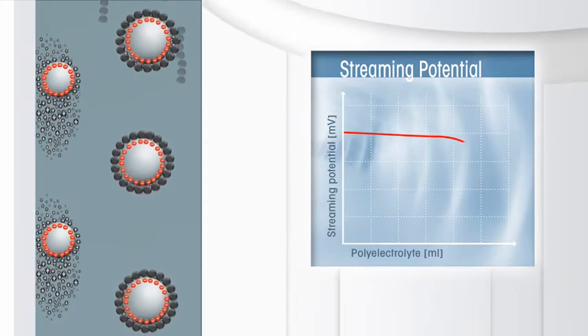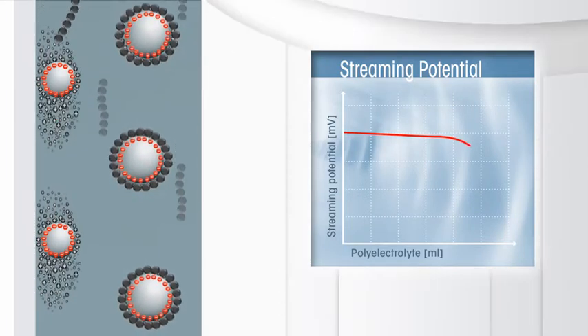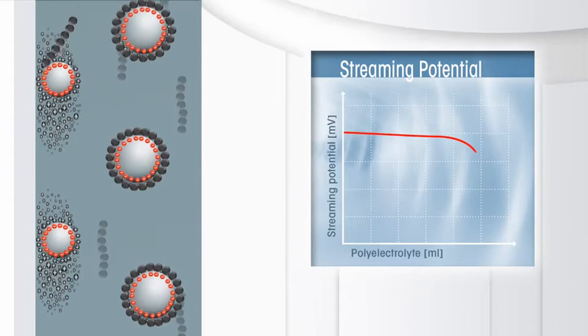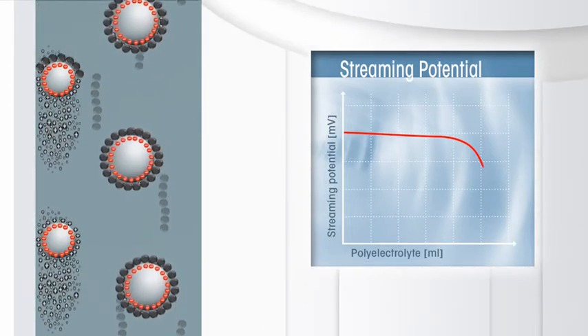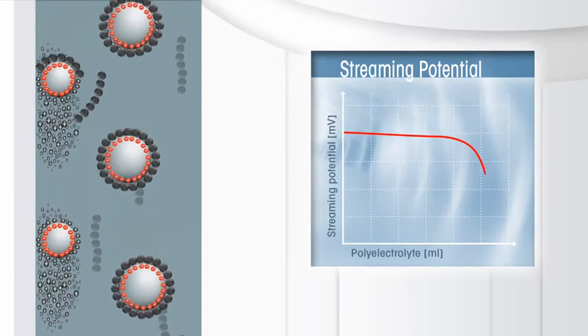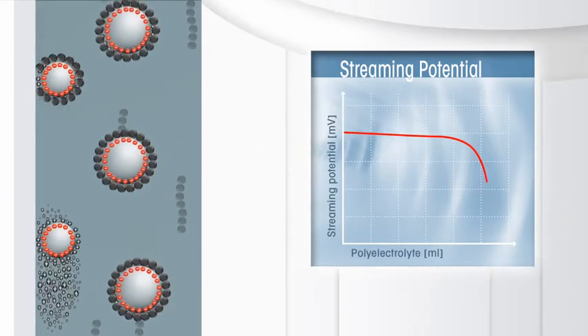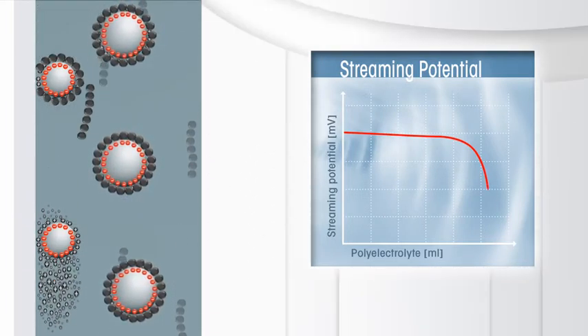The adsorbed particles are then neutralized by the titrant. These fixed particles have a strong influence on the height of the streaming potential. Their neutralization is reflected in a fast-decreasing measuring signal in the particle charge detector.